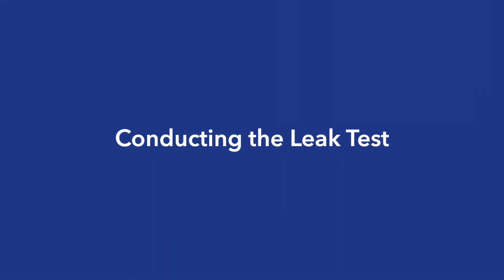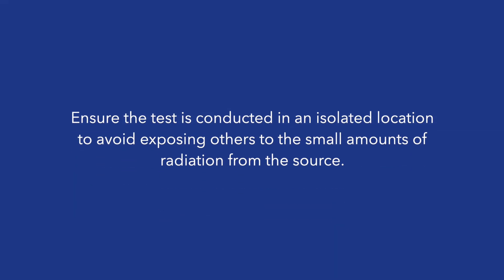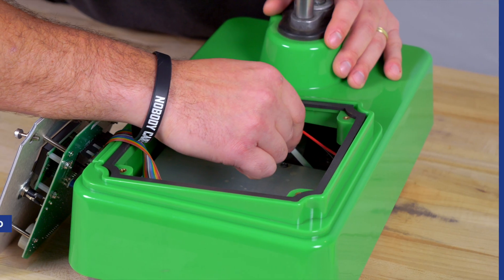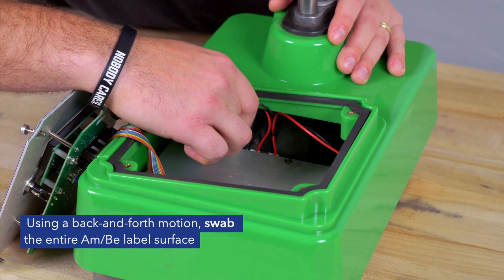Conducting the leak test. Ensure the test is conducted in an isolated location to avoid exposing others to the small amounts of radiation from the source. Using a back and forth motion, swab the entire Am/Be label surface.